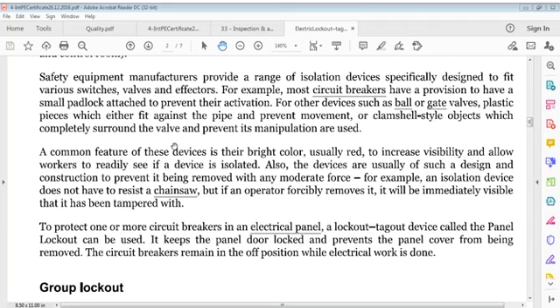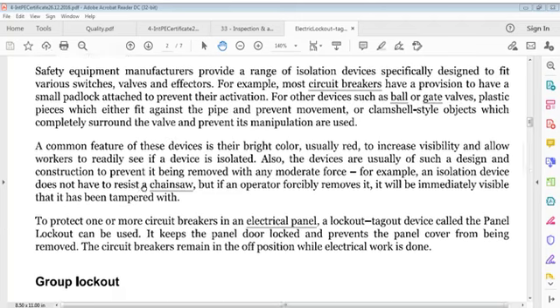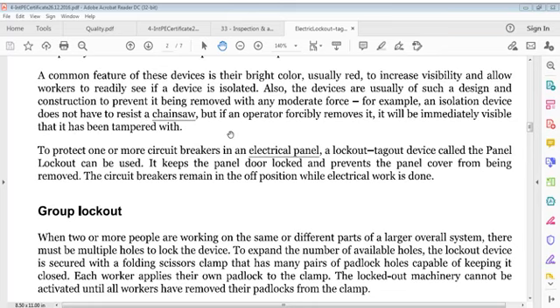provide a range of isolation devices specifically designed to fit various switches, valves and effectors. For example, most circuit breakers have a provision to have a small padlock attached to prevent their activation. For other devices such as ball or gate valves, plastic pieces which either fit against the pipe and prevent movement, or clamshell style objects which completely surround the valve and prevent its manipulation, are used. A common feature of these devices is their bright color.